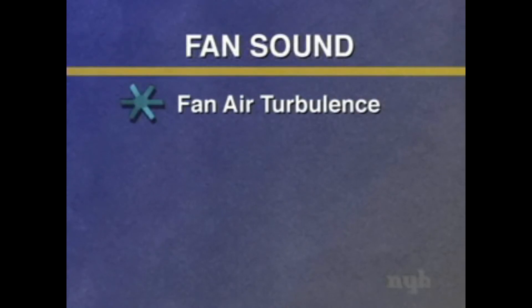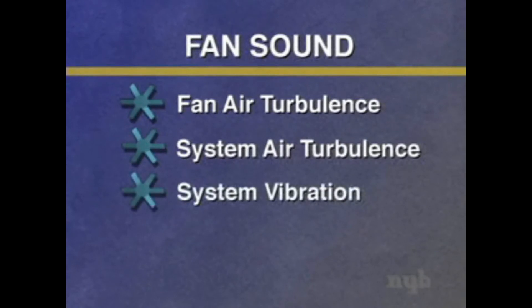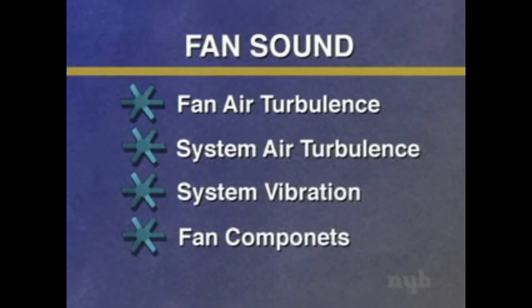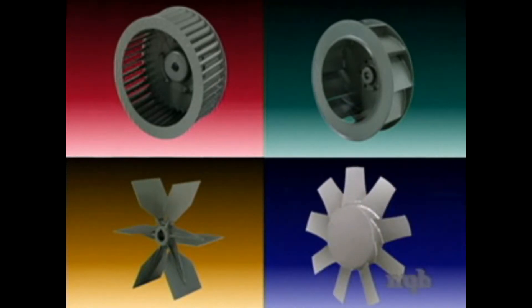Fan sound is generated in four basic ways: fan air turbulence, which is dependent upon the fan wheel design; system air turbulence; system vibration; and fan components. Because there is a wide variety of different flow, pressure, and gas stream requirements, a variety of different fan designs have been developed. For example, there are three basic centrifugal wheel designs: forward curve, backward incline, and radial. There are also a variety of axial wheel designs. As you might expect, each has unique sound characteristics.